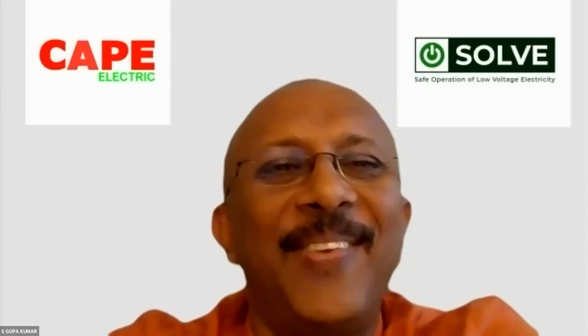Could you please share any electrical safety lesson learned from disasters such as flood? Is there any study that is done? Of course, this is another big point. Actually, in the IEC TC64, which is the low voltage electrical safety standards, Japan has proposed a new standard, a resilient electrical installation. That means, in case of a disaster, how fast it can be put back to service. With respect to the floods in India, if the electrical installation was under water for some time, then be very careful. Before putting it into service, you have to do an insulation resistance test at least. If you do the insulation resistance test, you are sure that the connected things are perfect.